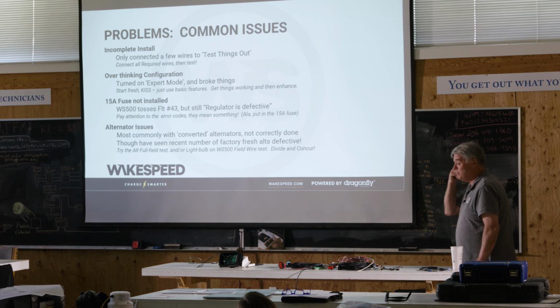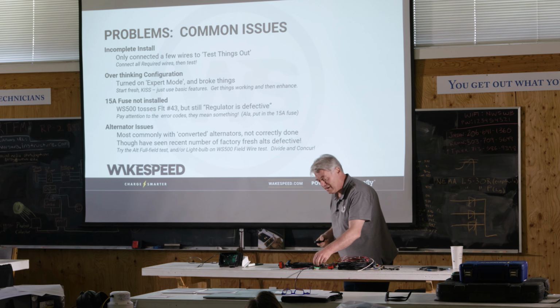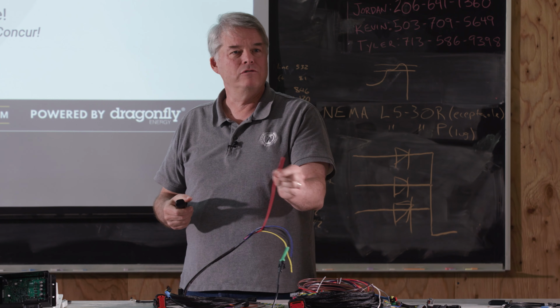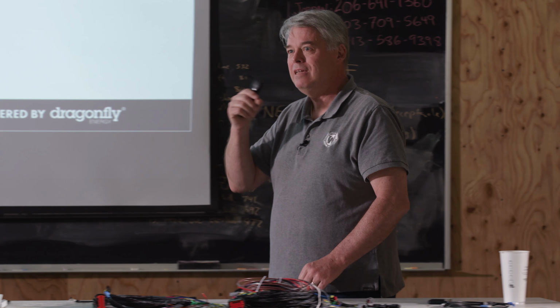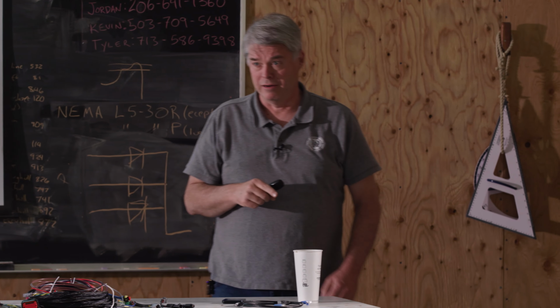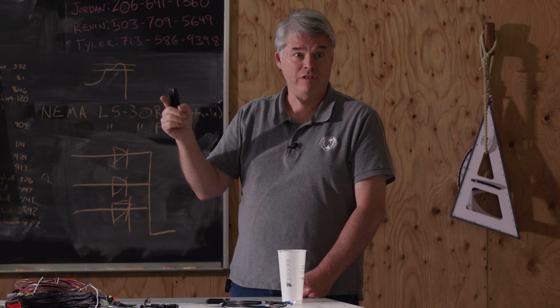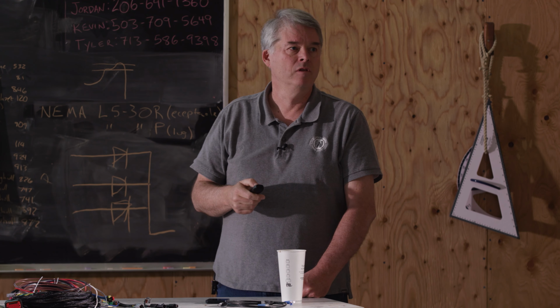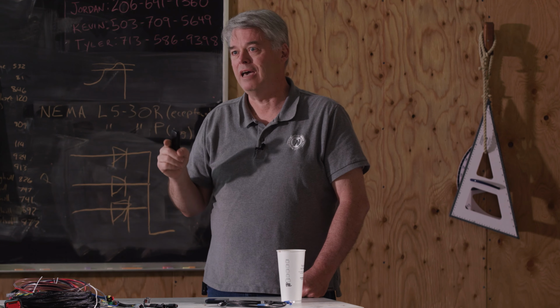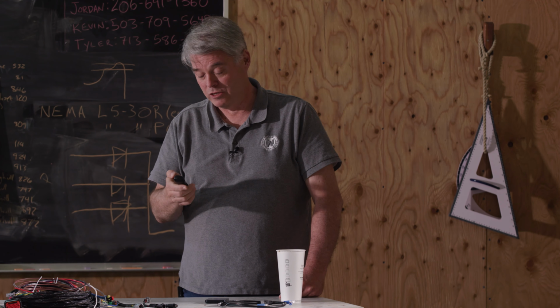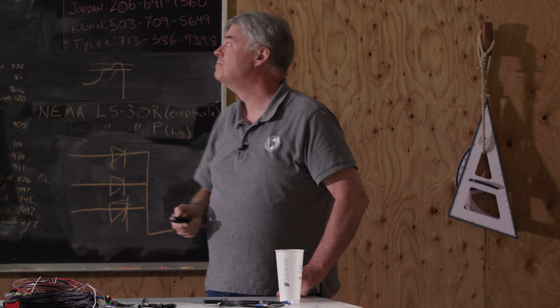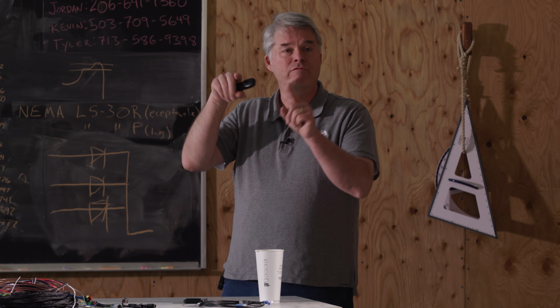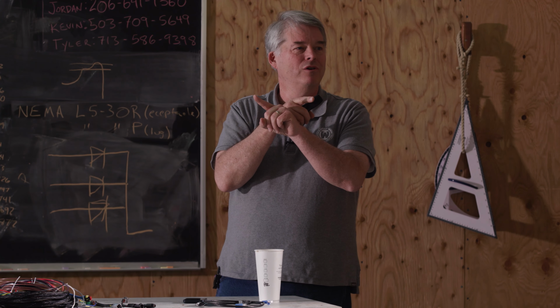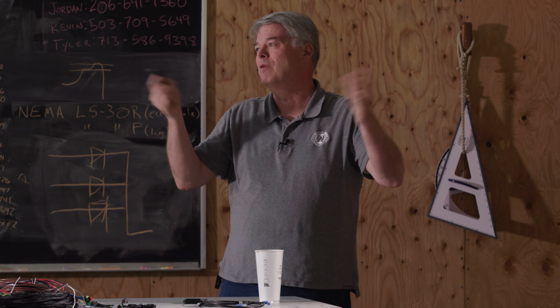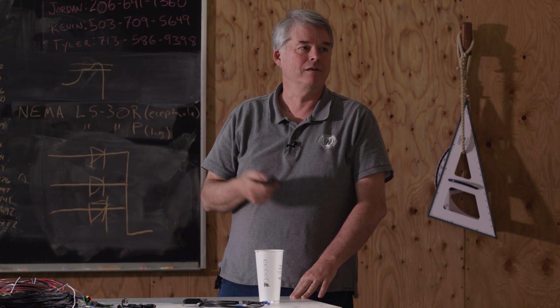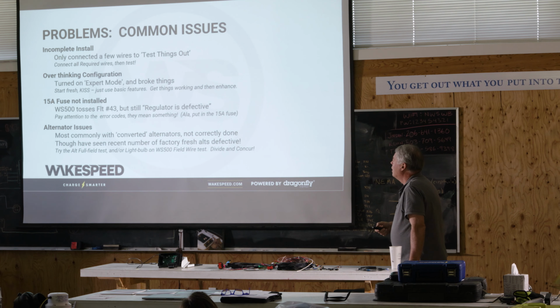The 15 amp fuse - you'd be amazed how many calls we used to get because that 15 amp fuse on the red wire wasn't installed. So many, in fact, that version 2 of the regulator will throw a fault if it doesn't see voltage on that red wire. But with version 1, we don't sense that, and that's a good reason why the Wakespeed won't drive the alternator - no power. Or they reversed the 15 amp and 3 amp fuse - they put the fuses in, but reversed them, and the moment they started to drive the alternator, that 3 amp fuse opened because it just wasn't up to it.